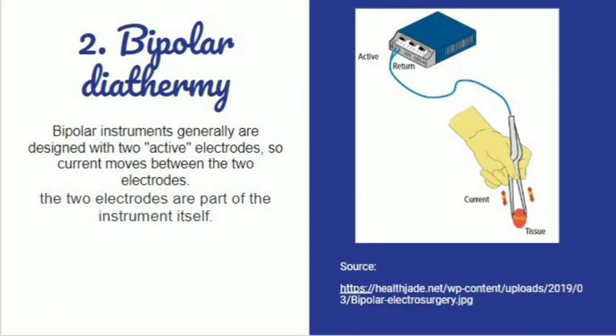The second type is bipolar diathermy. Bipolar means two poles — two active electrodes and no ground electrode. Bipolar instruments are designed with two active electrodes so current moves between them; the two electrodes are part of the instrument itself. As you can see in the figure, they are side by side attached to each other, and they look like a forcep or tweezers more precisely.